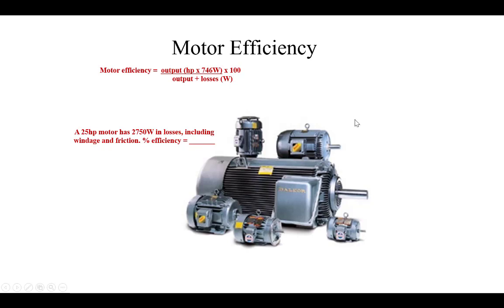Again, it should be fairly straightforward to solve if we find the watts output over the watts input. Whenever we see a rating on a motor, if it says 25 horsepower on the motor nameplate, that is always the output of the motor. The input, of course, will be the output plus the losses. So in this case, the motor efficiency is 87%. That's really all there is in Objective 1: a couple of formulas to know and a couple of definitions to be aware of.